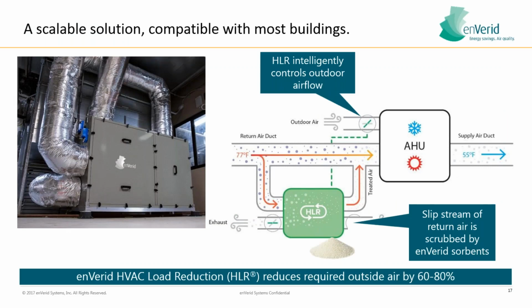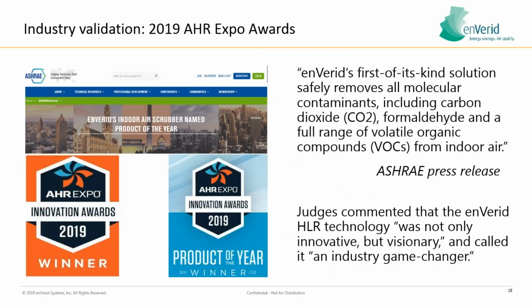So we talked a little bit about the integration here. You can see the enVerid box, the enVerid HLR, off to the side there. It's a 2 foot by 4 foot by 6 foot box. It can lay on its side or be oriented vertically as well, and is a side stream air scrubber that continues to remove all contaminants of concern.